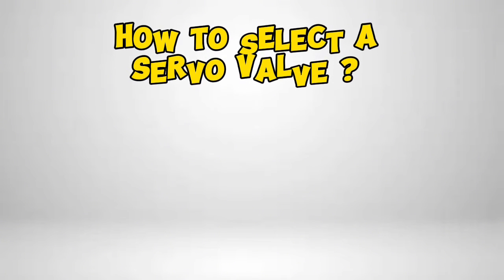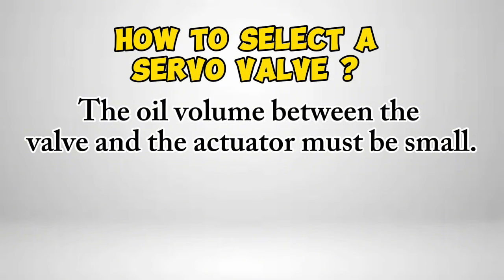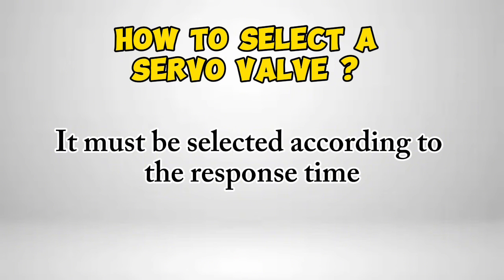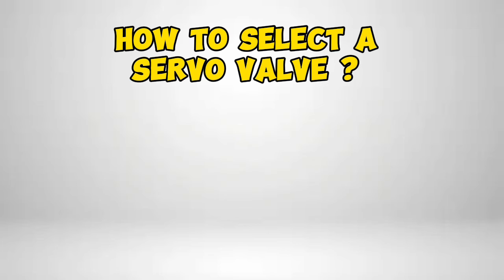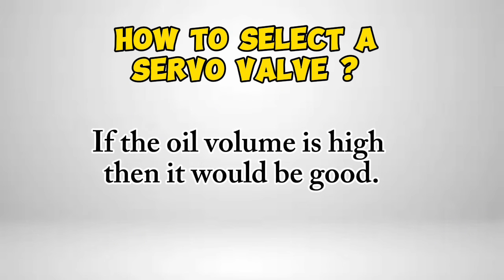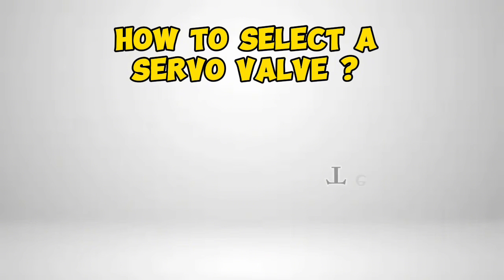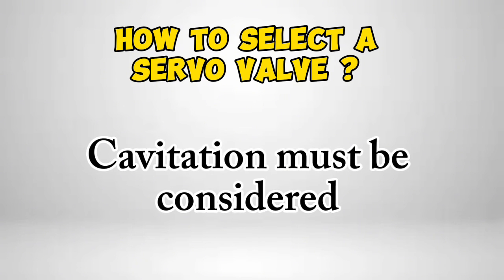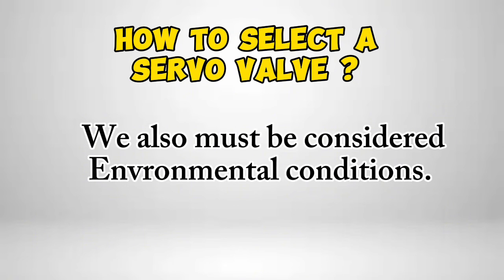How to select a servo valve. The oil volume between the valve and the actuator must be small. It must be selected according to the response time. We must consider the flow pressure gain. If the oil volume is high, then it would affect performance. Other factors to consider include installation position, temperature range, vibration, cavitation, and environmental conditions.